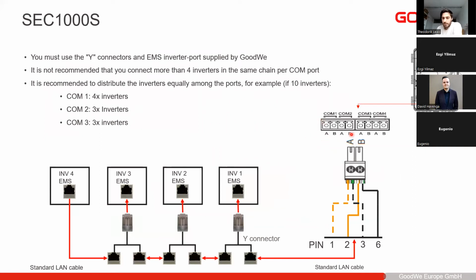Here you see the connection. So here, this is on the SEC1000S. How you connect it is 4 comms, and you connect it to COM 1, 2, and 3. And then you go into the Y connector like this, and then the other side goes to the inverter, and the second side goes connecting to the other inverter, and so on. And you can connect up to 10 inverters to one SEC1000S.